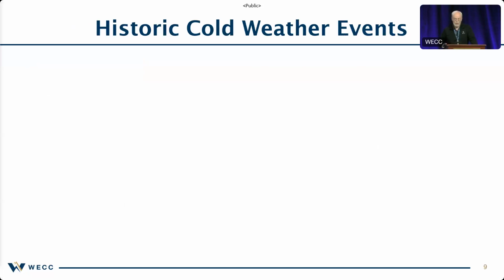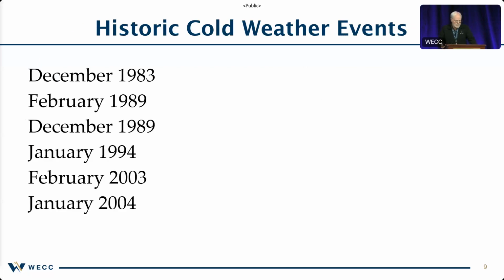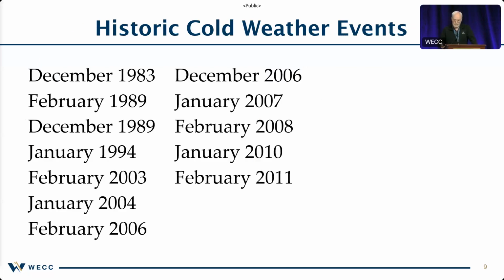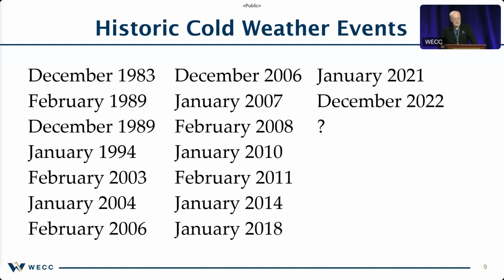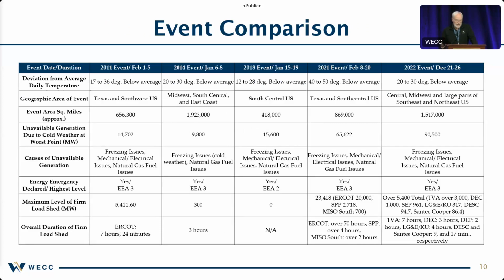So when we look at cold weather events that are on the NERC website, what we see is they've got records of about 16 different events that occurred over the last 40 years. Of those 16 events, 12 of them occurred within the last 20 years. We're going to talk a little bit today about just the last 5 events. But we can see that with all of these events that occurred, they did an investigation. They came up with reasons why it occurred. They came up with recommendations, things to take care of that might help. But we still have events occurring. And without some sort of intervention, like cold weather standards, the next event really is a matter of when rather than if. So we look at an event comparison of just the last 5.